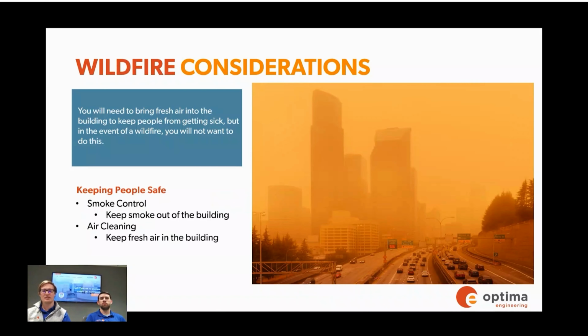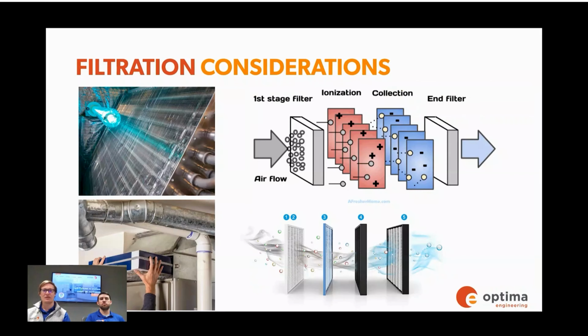Another disaster consideration is wildfires. I mentioned ventilation earlier - people breathing generate CO2 and other contaminants, which our design usually flushes out using fresh air from outside. But in a wildfire situation, that outside air is actually in worse condition than the air quality inside. So we design systems to shut that normal open ventilation and clean the air inside in a closed loop.